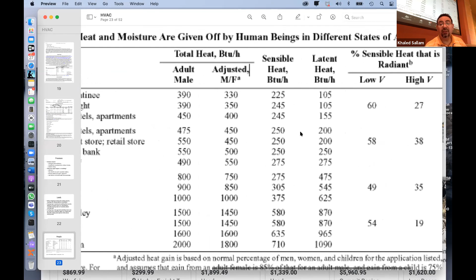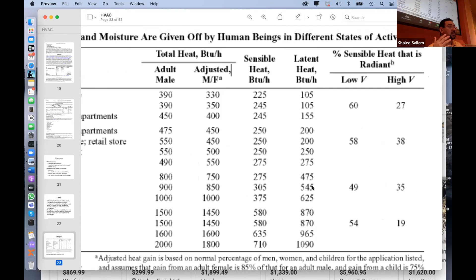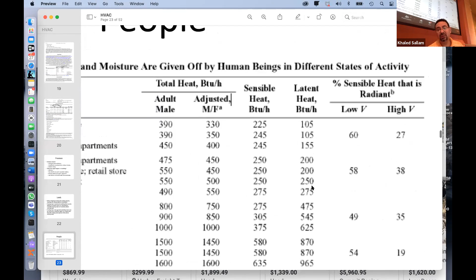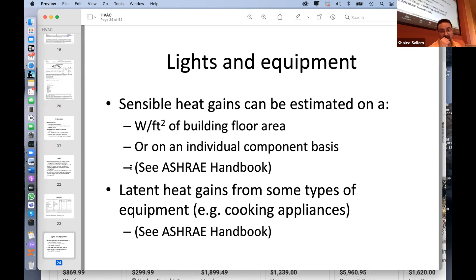So the sensible is just like dry heat that they send, and latent heat is simply their m dot h_fg, m dot of steam they are sending out times h_fg, latent heat of evaporation. Okay. So you add the people and you add the machine. For example, the lights. They tell you the lights is simply watt per square foot of building. So if you know the area of the corridor or the area of the auditorium, you can basically say, well, that will require this much watt. Okay.